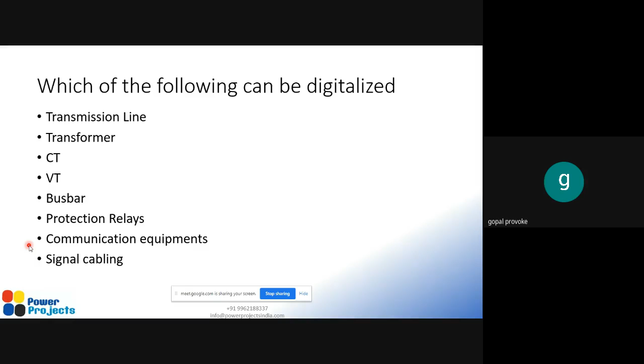So this equipment cannot be digitalized: transmission line, transformer, bus bar, insulator, and again circuit breaker. I have not mentioned it, but circuit breaker. These kinds of equipment cannot be digitalized. These are all physical equipment which we need physically to transmit the power. We need the transmission line, the transformer, the bus bars, insulators, and circuit breakers. So we cannot digitalize this equipment. It is needed physically for transmitting the power. But this equipment can be digitalized: protection relays, current transformers, voltage transformers, communication equipment, the SCADA equipment, signal cables. Although we call it a digital substation, only this equipment can be digitalized. But we still need the transmission line and the transformer, those kinds of physical equipment for converting the power and transmitting the power.